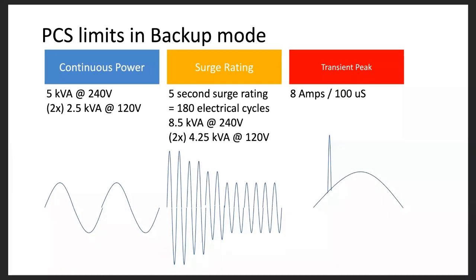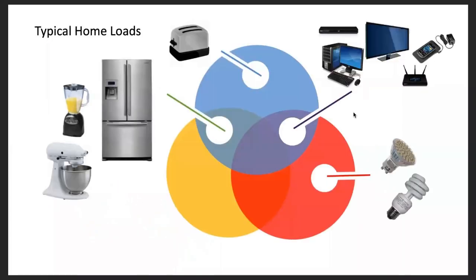That's a pretty basic assumption, but needs to be mentioned. It has a surge rating of maximum of 5 seconds at 170% of nameplate. And again, that's 8.5 kVA at 240 volts, and you can do the math here. And then it will also withstand transient peaks of 8 amps for 100 microseconds. So I won't get into too much detail here, but we will look at how to measure these loads and what types of loads fall into what categories. Typical home loads, for example, this toaster oven would be a continuous power requirement. Any resistive load is a purely continuous load and is pretty easily accounted for.